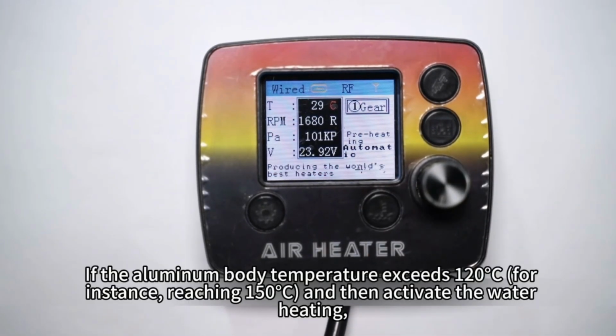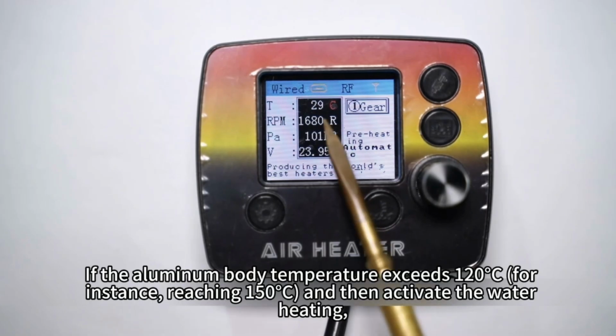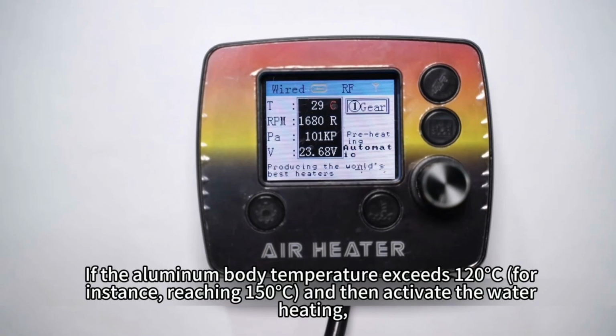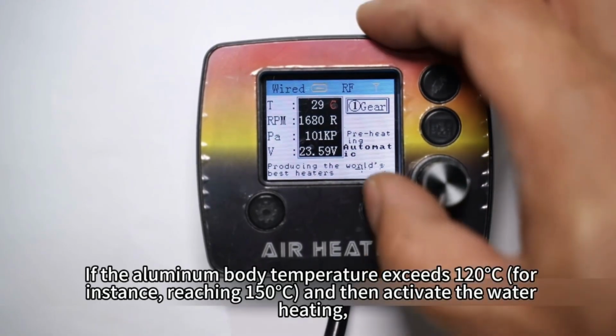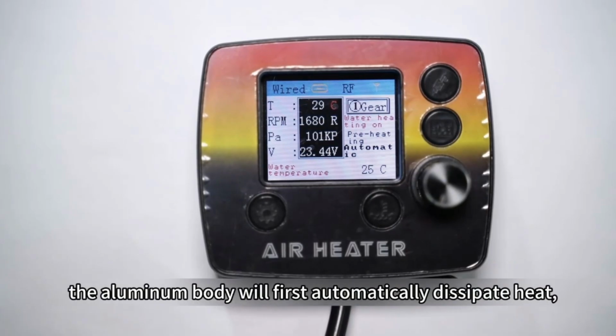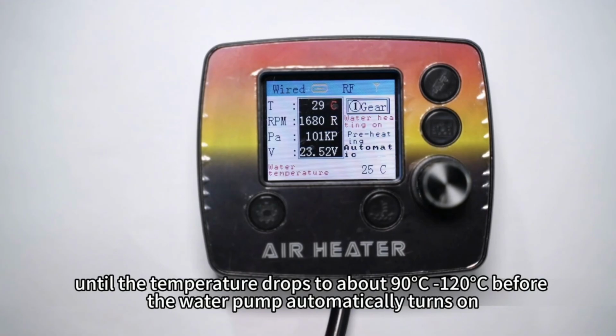If the aluminum body temperature exceeds 120 degrees Celsius, for instance, reaching 150 degrees Celsius, and then you activate the water heating, the aluminum body will first automatically dissipate heat until the temperature drops to about 90 to 120 degrees Celsius before the water pump automatically turns on. This design is implemented to prevent thermal expansion and contraction.